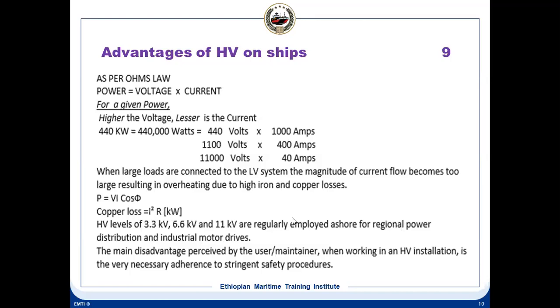Now, if you look at this slide, you see here it says for a given power, 440 kilowatt. That works out to be 440,000 watt. Suppose you have a generator of 440 volt. To have that 440 kilowatt power, your current is going to be 1000 amps at 440 volt. But for the same power, 440 kilowatt, if you increase the voltage to 1100 volt, the current is reduced to 400 amps. If you further increase the voltage from 1100 to 11,000 volt, the current is reduced to 40 amps for a given power. This is very important, for a given power. So what we can observe is that as you increase the voltage, the current comes down.